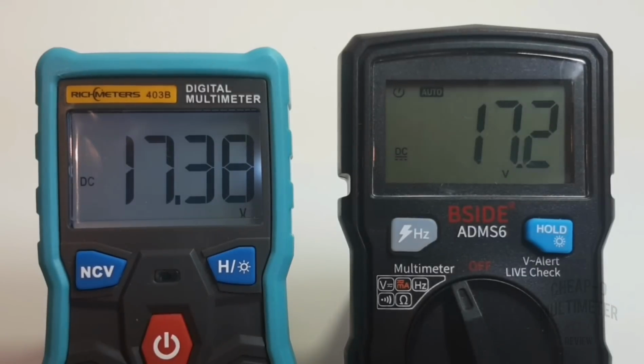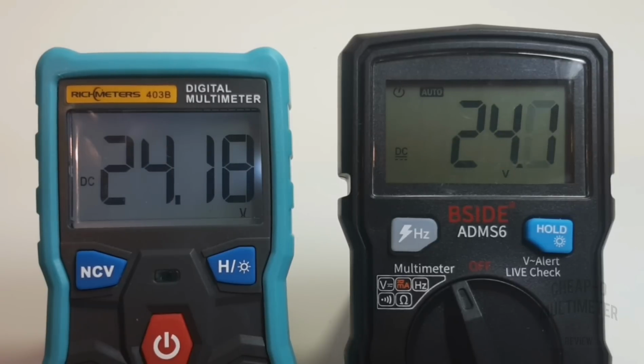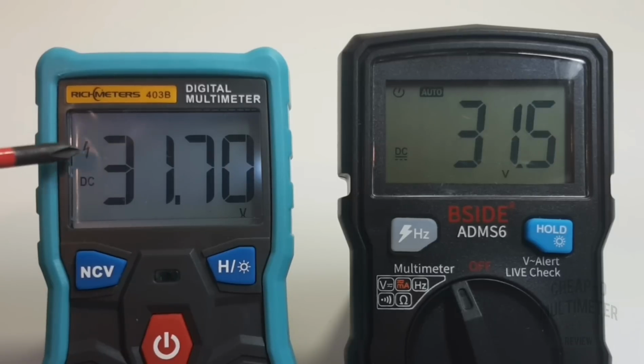I hope we can see that alright. Going up to 24 volts even: 24.19 for the rich meter, 24.0 spot on for the B side. Okay, we're going to max it out now up to 31.5 volts. We have the high voltage indicator on the rich meter, as you can see right here, nothing of the sort on the B side. 31.7 volts for the rich meter, 31.5, pretty well neck and neck for the B side.